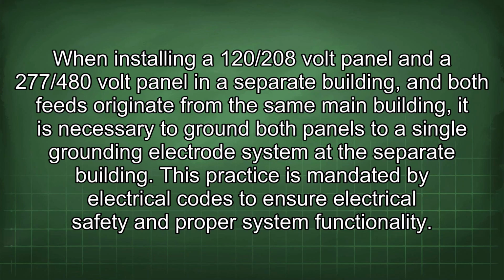When installing a 120/208 volt panel and a 277/480 volt panel in a separate building, and both feeds originate from the same main building, it is necessary to ground both panels to a single grounding electrode system at the separate building. This practice is mandated by electrical codes to ensure electrical safety and proper system functionality.